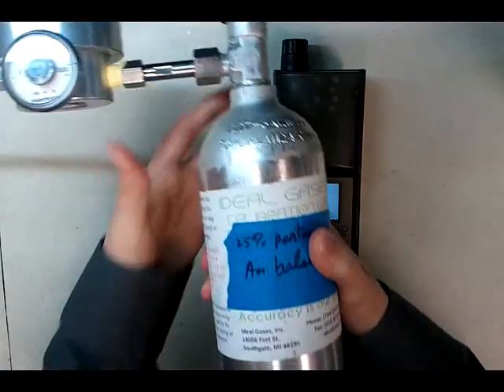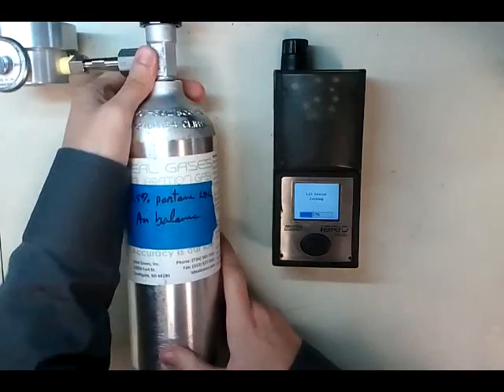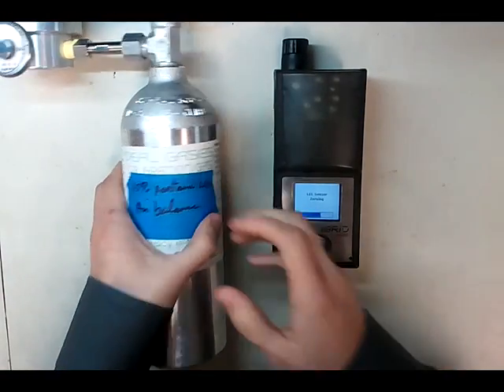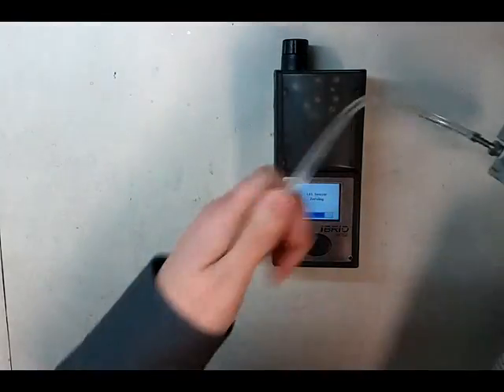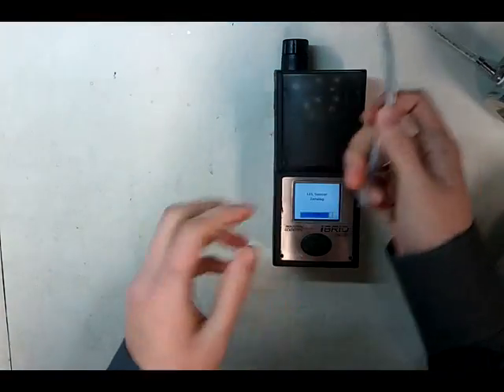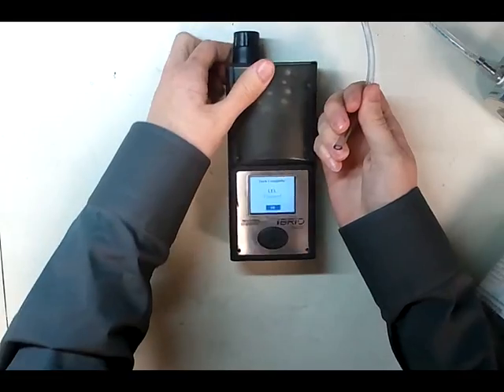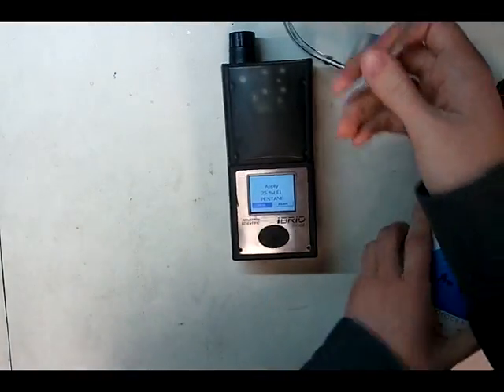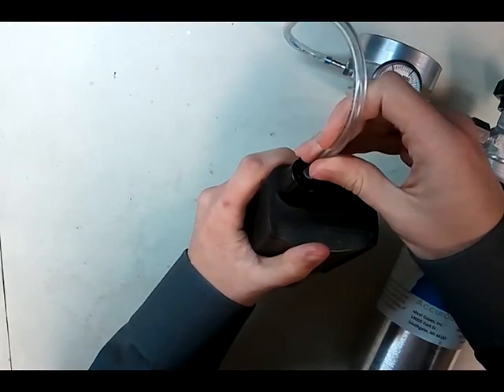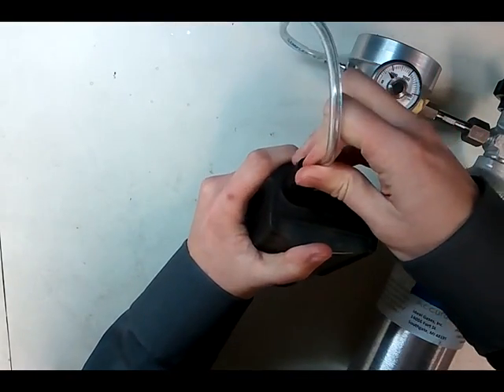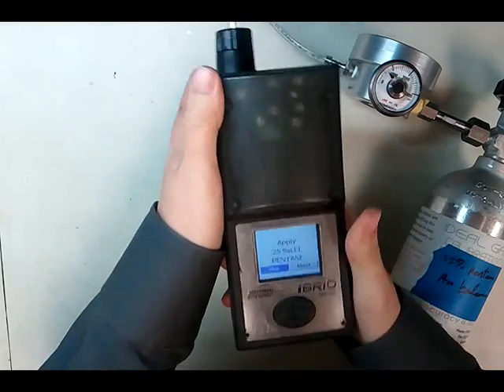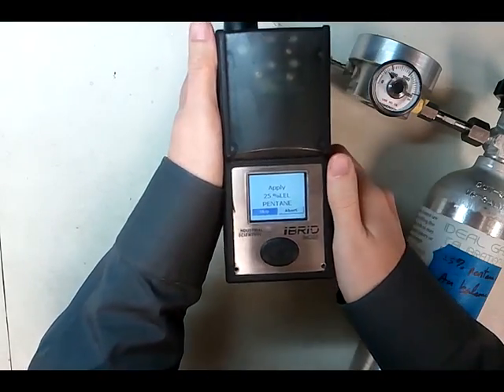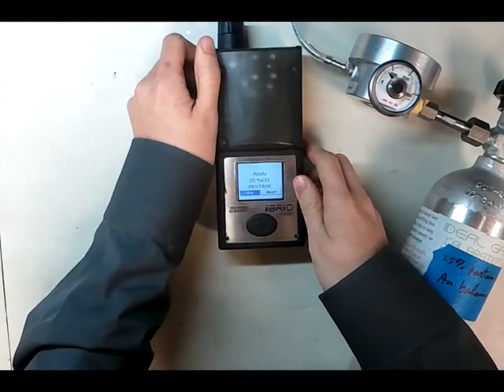Meanwhile, I've got a blend of 25% LEL pentane calibration gas that Ideal Gases put together for us, and I've got a nice demand flow regulator here. We'll be plugging this in and letting it calibrate.